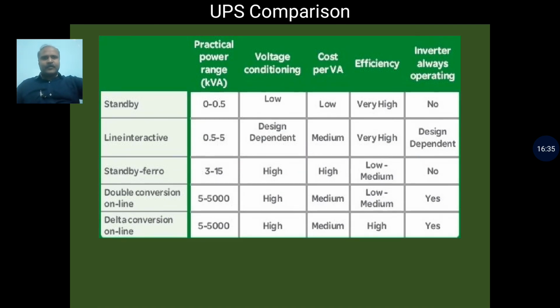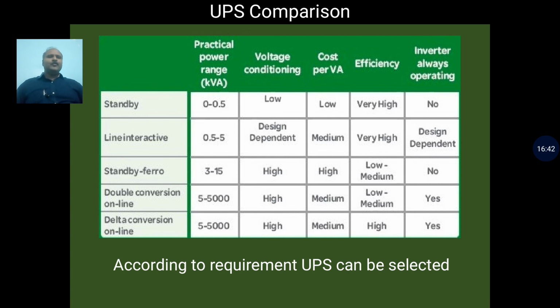Here we have a kind of summary, or UPS comparison. According to the requirement, a UPS can be selected, meaning according to the power requirement, voltage conditions, efficiency, and the requirement for switching time delay. If switching time delay is acceptable, then a standby inverter can be suggested. For hi-fi equipment, scientific electronic equipment, or any computer or data center servers, double conversion is the one to choose, because switching time is absolutely zero in that case, as it provides online UPS action.